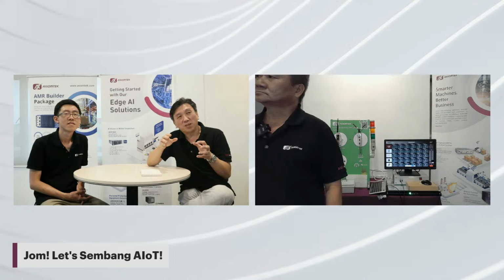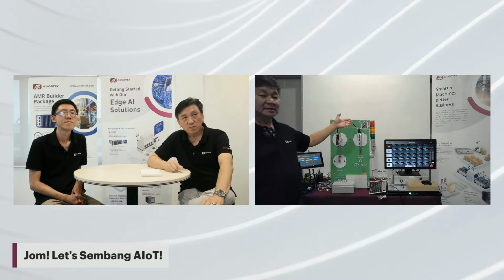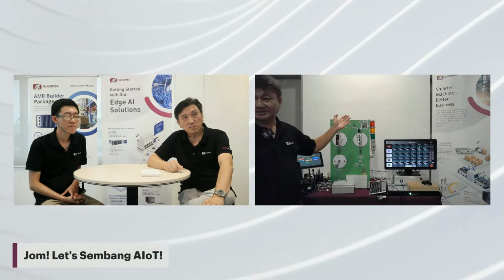How is this stack light tracker installed in a real production floor? For example, we want to track OEE from one particular process. Actually, I just need 3 data. I want to know the status of the process, I need the cycle in, and I need a count output. From this stack light, you can see orange and green. Orange, of course, is stop. We know, stop is a stop, it means that the machine is at downtime. Then the orange color we are tracking as a count output. Green color is a cycle in. So from these 3 signals, I can generate OEE with the insight.